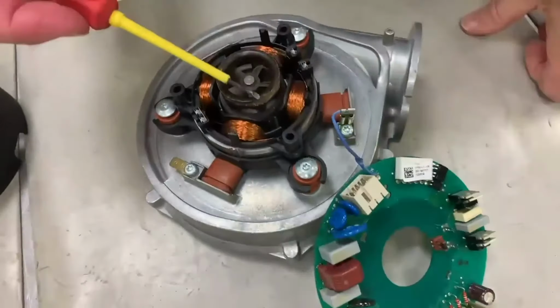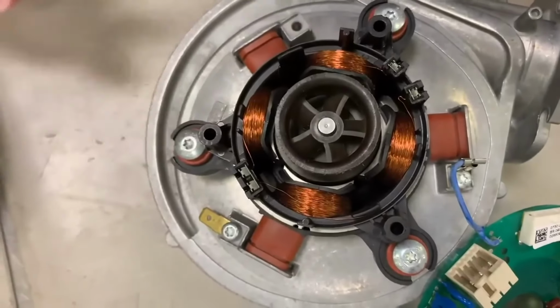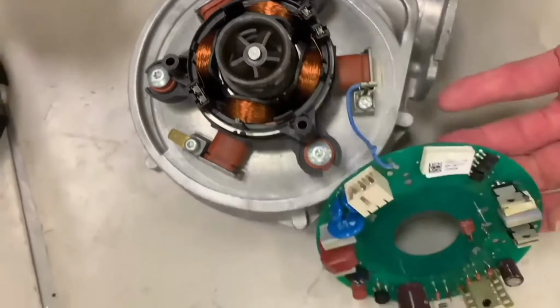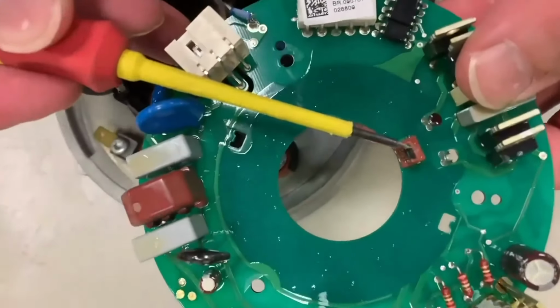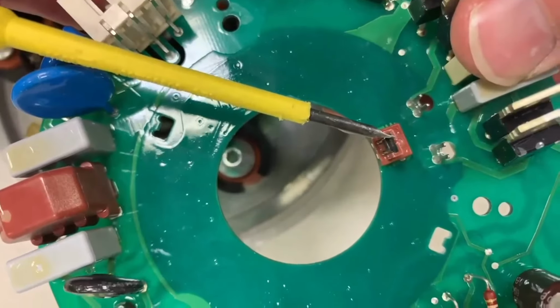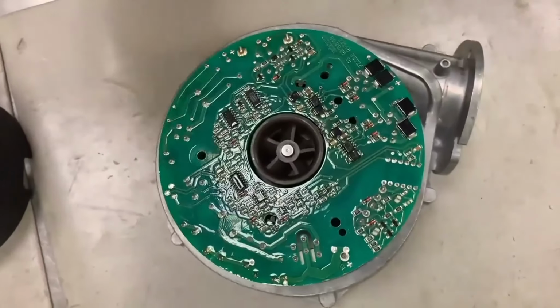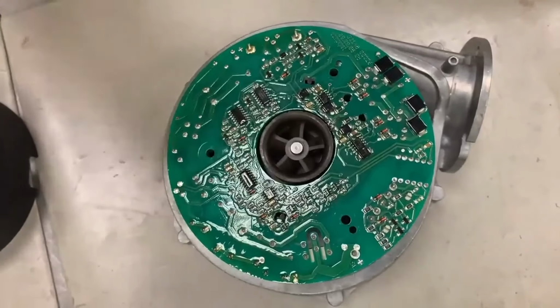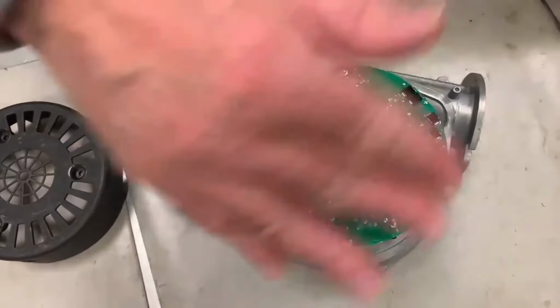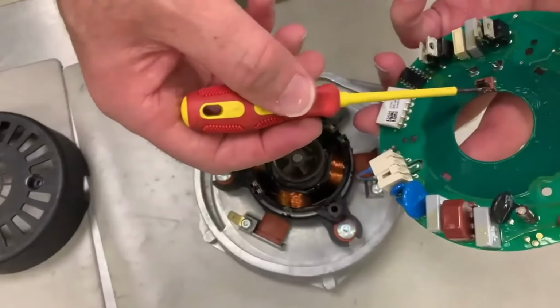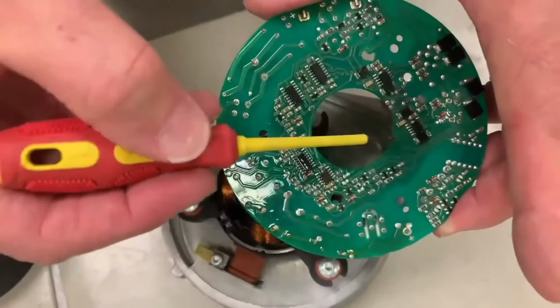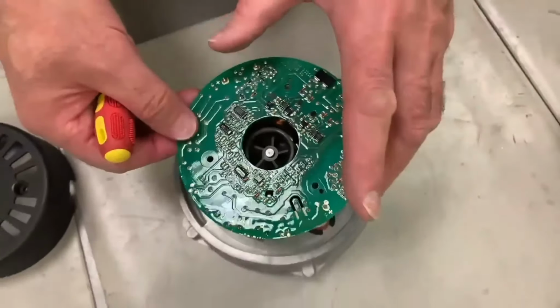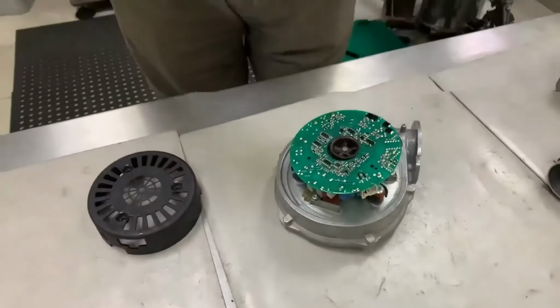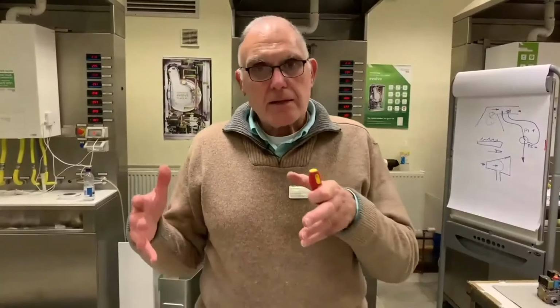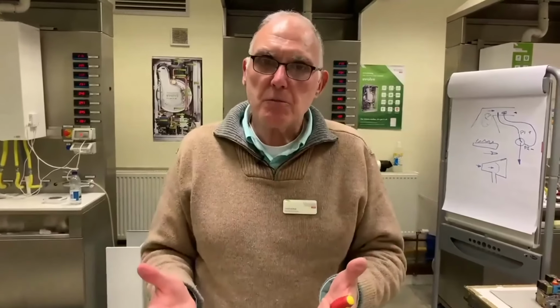So buried in the rotor here, there are tiny magnets. They flash by this device here, which is part of the Hall effect sensor. This rotates, and as it spins, we're getting a series of blips coming back down to the board. So somewhere here, or maybe in this circuitry here, it's broken down. So the fan motor's okay, the Hall effect sensor had failed. That's fans. That just about wraps up testing components this evening.